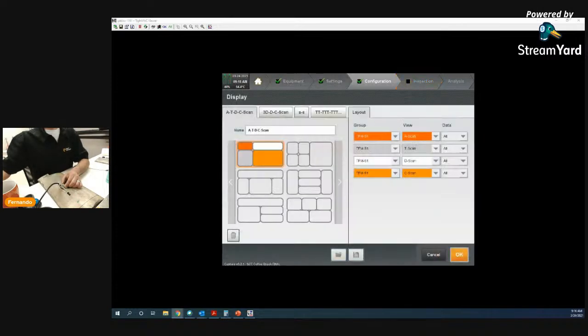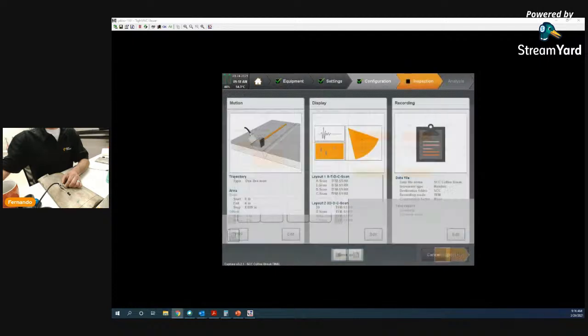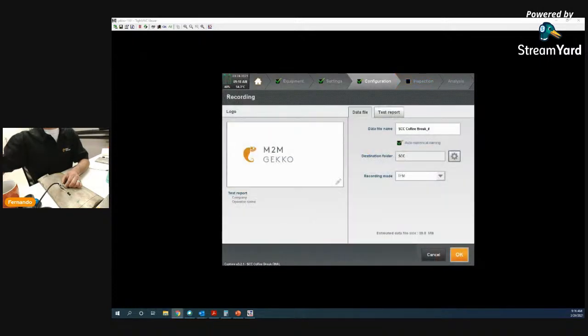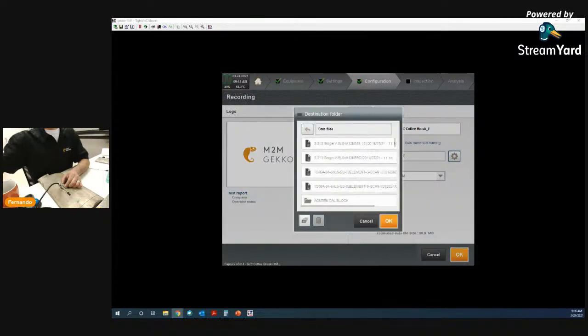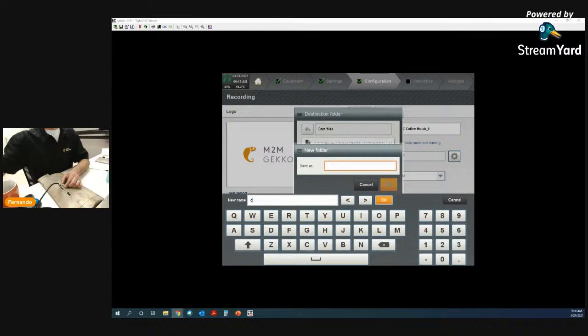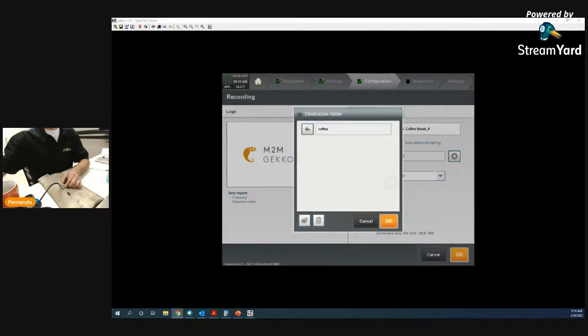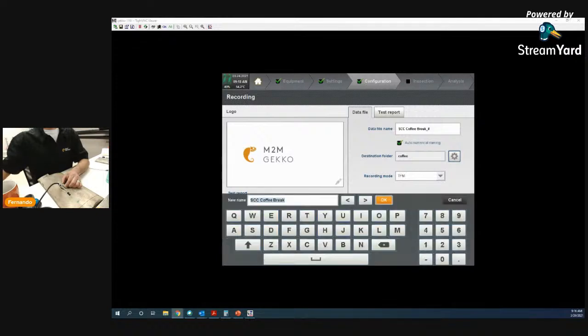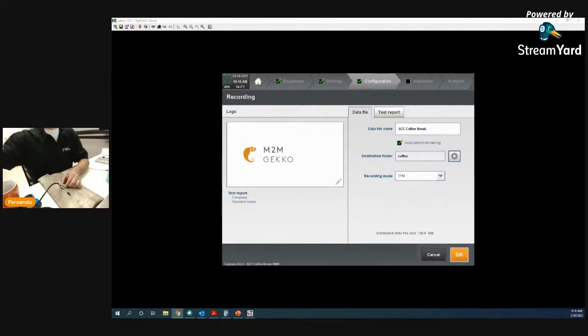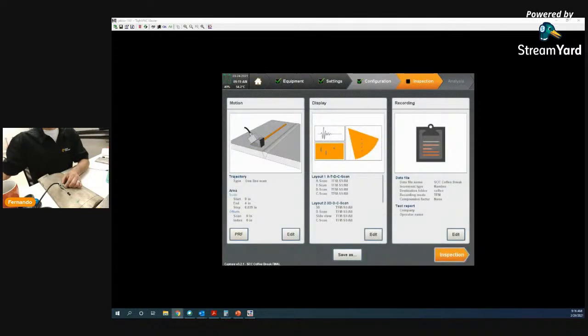So I can go to my displays. You can see right now I'm gonna set up an A scan. T scan is pretty much like an S scan for TFM. D scan is a side view. C scan is a top view. So I go edit. One thing that you can do here is create a folder. So this is coffee. Hit OK, OK, OK, and that's the data file I want to save. It's going to save it into that folder, instead of having to find the files that you inspected.